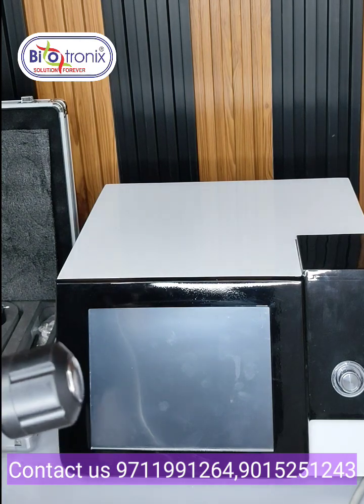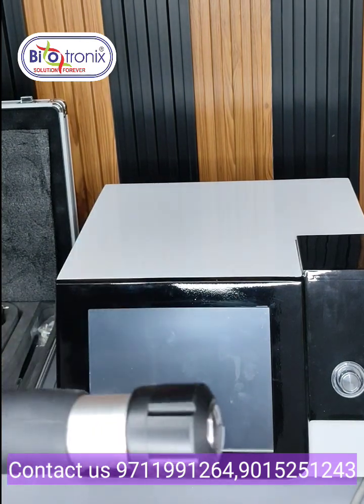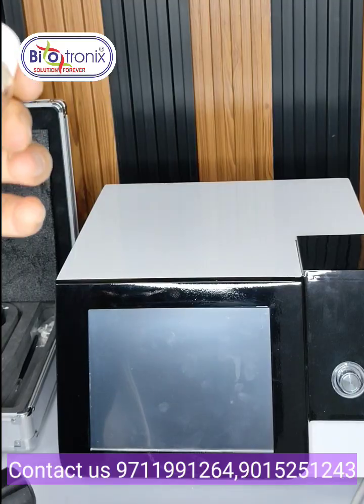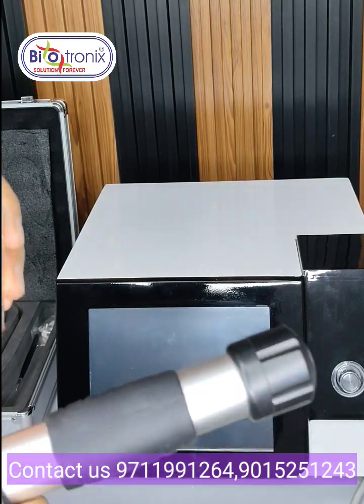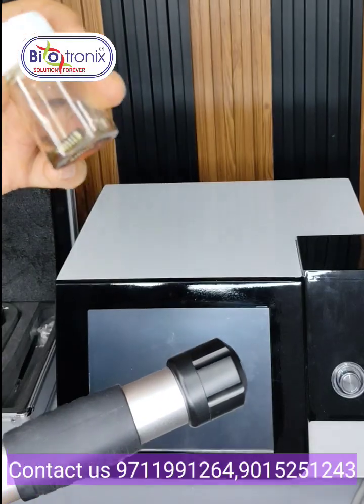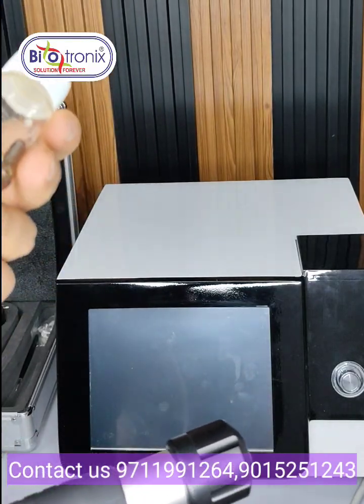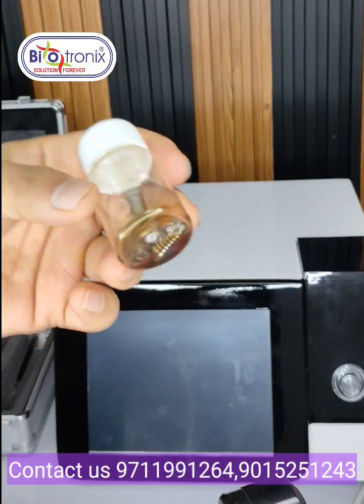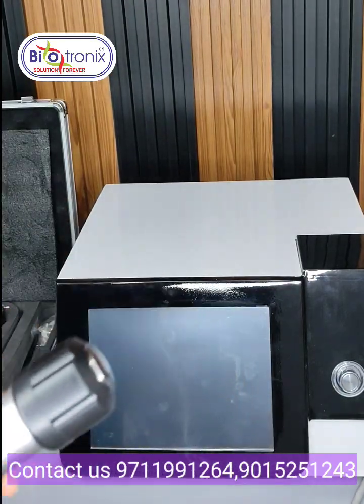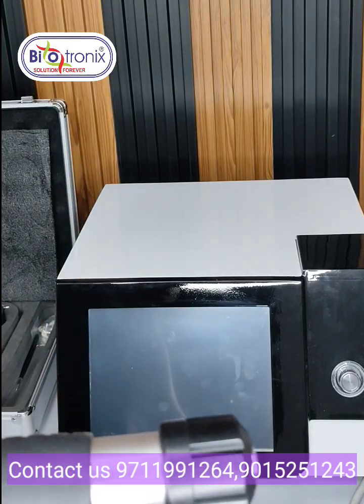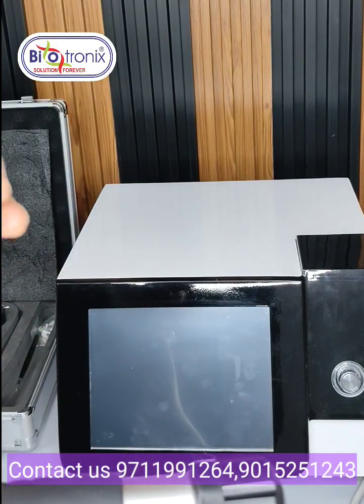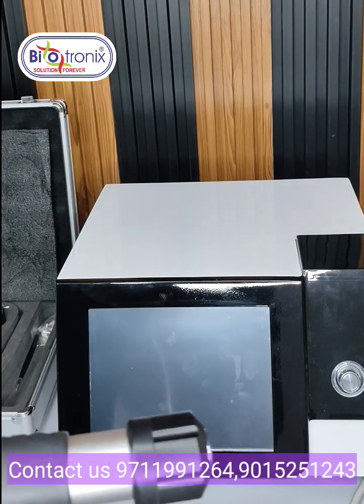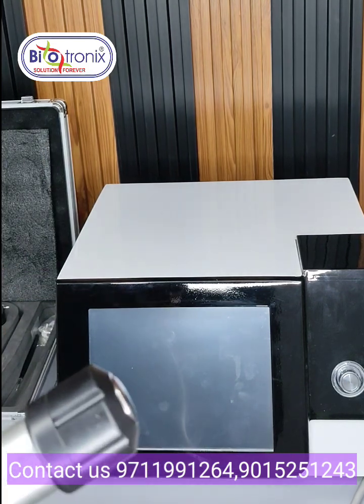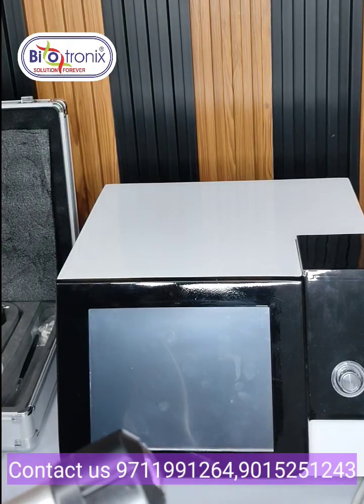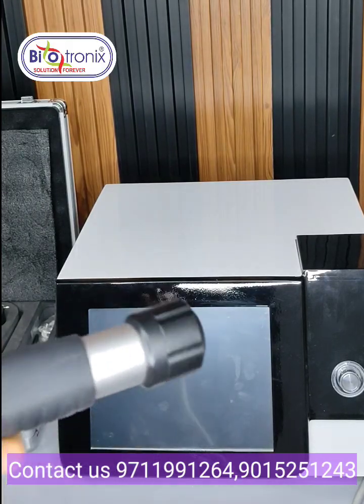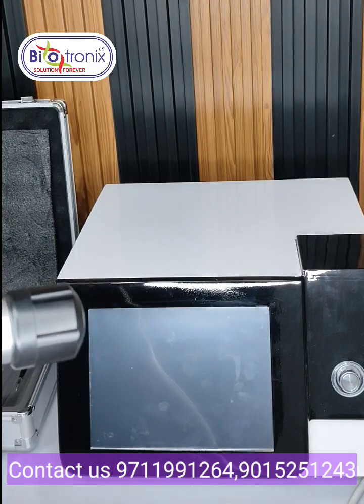So there is one bullet inside the probe, you can see, and there are 4 spare bullets we are providing with the same. So there are a total of 5 bullets. These are the 4 spare bullets. While the other models in the market don't provide spare bullets, or they just provide 1 or 2 spare bullets, we are providing 4 extra spare bullets, and one in the device. So a total of 5 bullets, and you are getting around 18 lakh to 22 lakh shots from the device, which is the maximum in the market. While other models in the market give around 10 lakh to 12 lakh shots. So after that you can buy the bullet as a consumable and then use the shockwave.